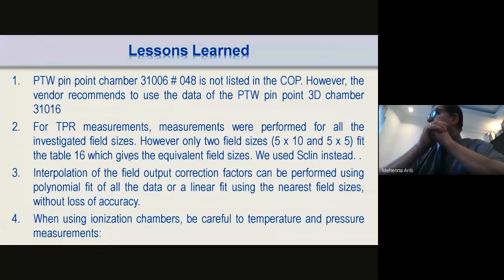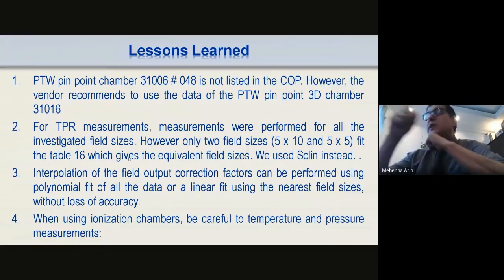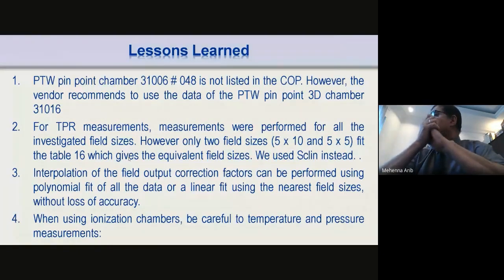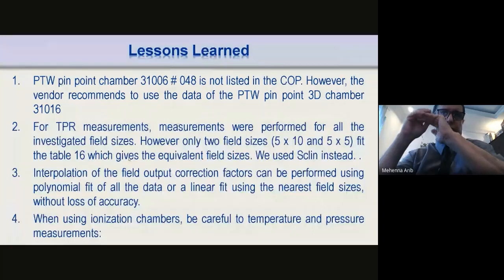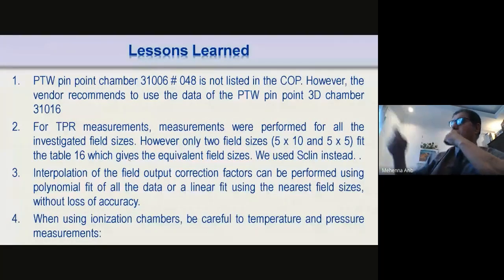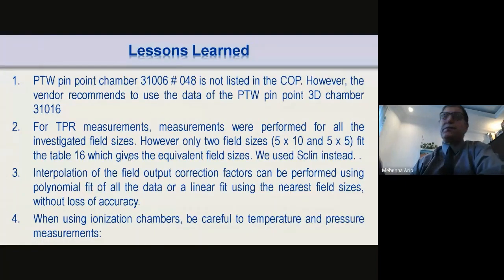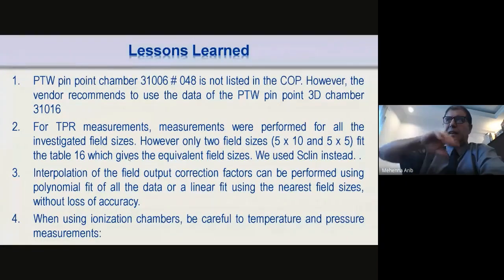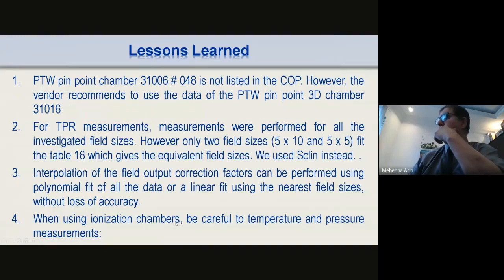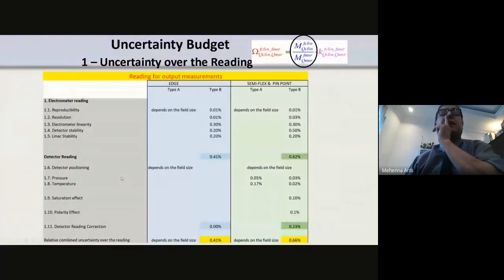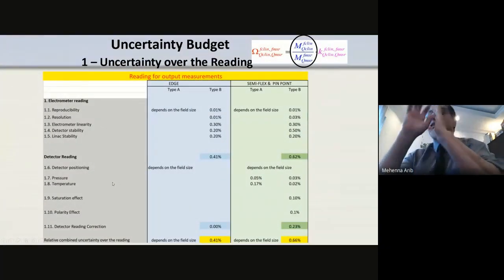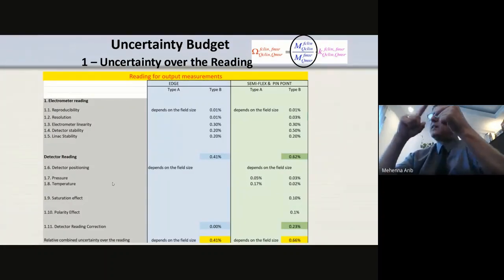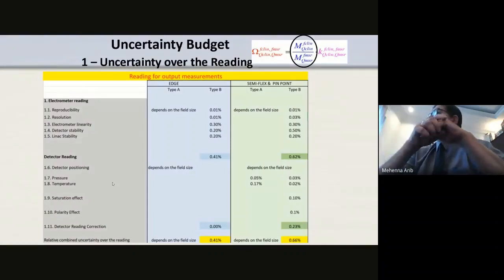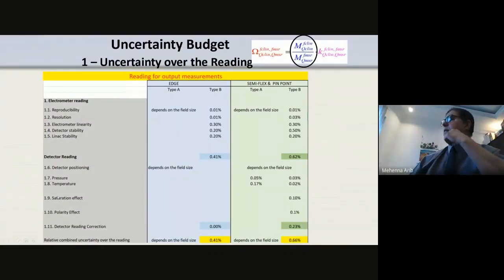And then the interpolation of the field output correction factor can be performed using a polynomial fit for all data, or linear interpolation using the nearest field size without loss of accuracy, which means that if you have, for example, a field size of 5 by 5, you can use the 5. You can, because it's the nearest field size. You can use linear interpolation. When using an ionization chamber, be careful with the temperature and pressure measurement. It's very important because the error on temperature measurement for small detectors is terrible. You have to put the thermometer close to the chamber in the water. Don't measure the temperature in air, because you get terrible results.